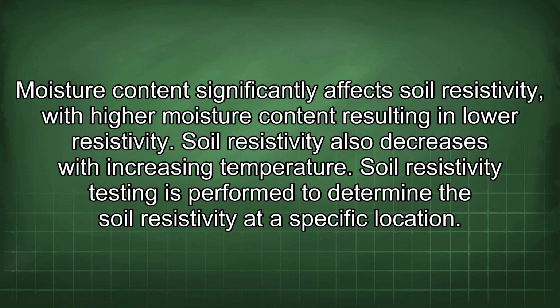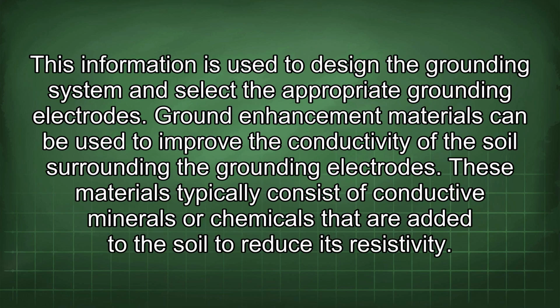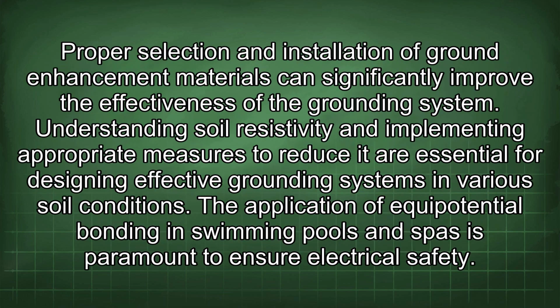Soil resistivity testing is performed to determine the soil resistivity at a specific location. This information is used to design the grounding system and select the appropriate grounding electrodes. Ground enhancement materials can be used to improve the conductivity of the soil surrounding the grounding electrodes. These materials typically consist of conductive minerals or chemicals that are added to the soil to reduce its resistivity. Proper selection and installation of ground enhancement materials can significantly improve the effectiveness of the grounding system. Understanding soil resistivity and implementing appropriate measures to reduce it are essential for designing effective grounding systems in various soil conditions.